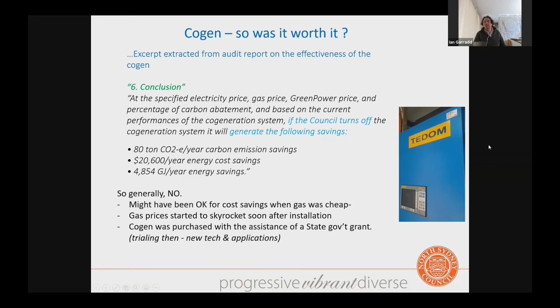So we could see pretty well straight away it was time to stop using the cogen system willy-nilly, which was actually running permanently before that time. After that, we've only been running the cogeneration system at times when we need a lot of heat and at peak periods, when the cost of electricity had potential to spike high, and also to minimise capacity charges. By really changing the control regime of the pool equipment, we could make significant savings. But overall, we could see it wasn't a good system to have anymore, certainly not anymore, because the cost of gas had gone up so much since we installed it.